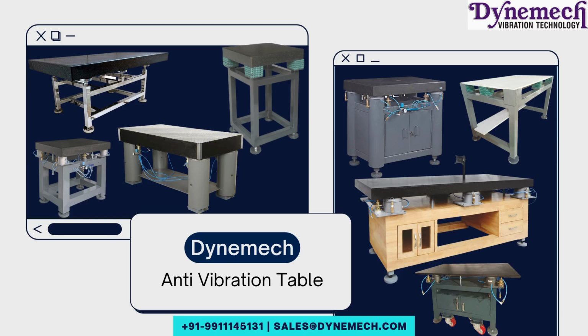Right, right. When should a customer select to use an anti-vibration table? In case the customer is sensing vibrations at the site due to disturbances from production machines installed nearby, or there is a construction site nearby, or machines are installed at higher altitude in a multi-story building. So the customer knows before installing sensitive machines that there are going to be vibrations and their readings will be affected with those vibrations, and then they may call us to conduct vibration measurements and to select the right anti-vibration tables for them.